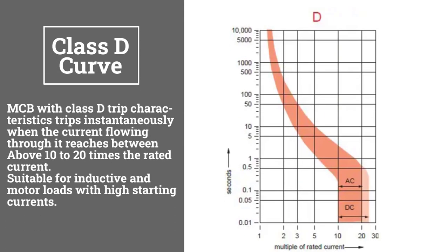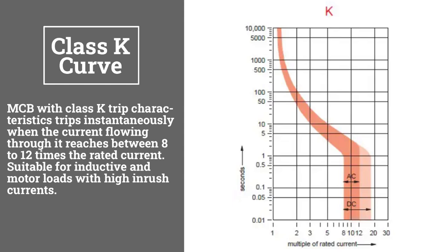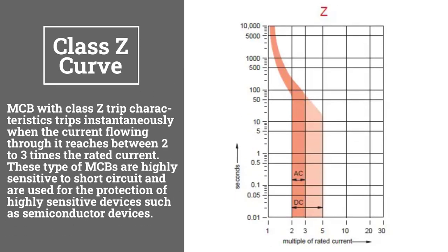Class D tripping current is above 10 to 20 times the rated current and it's suitable for inductive and motor loads with high starting currents. Class K tripping current is above 8 to 12 times the rated current. Class Z tripping current is above 2 to 3 times the rated current, so it's suitable for highly sensitive devices such as semiconductor devices.